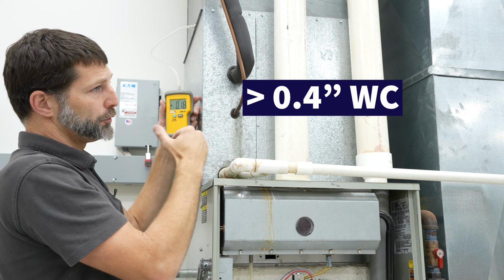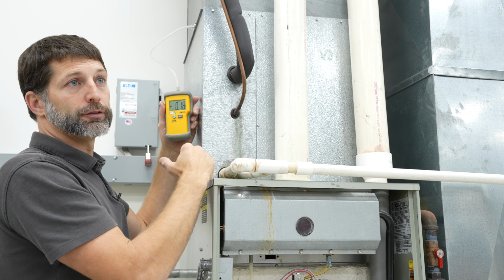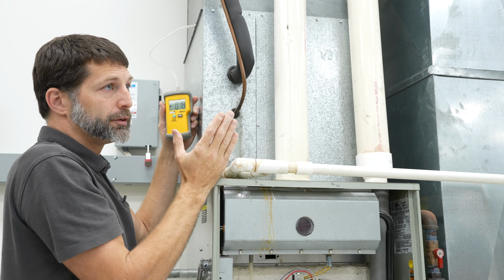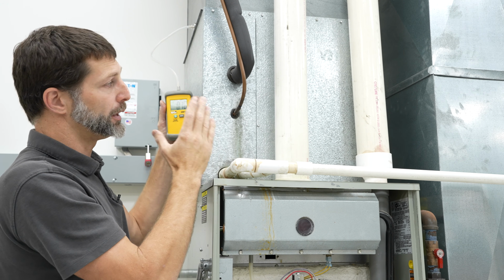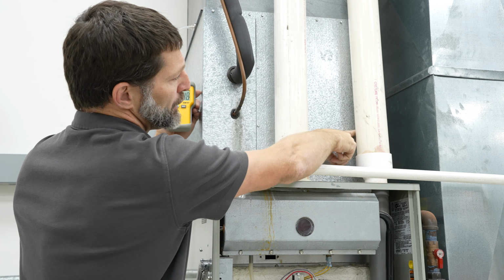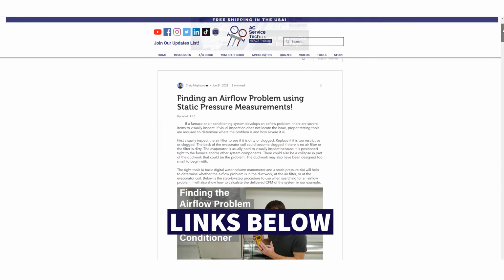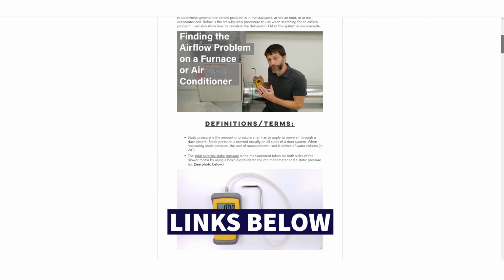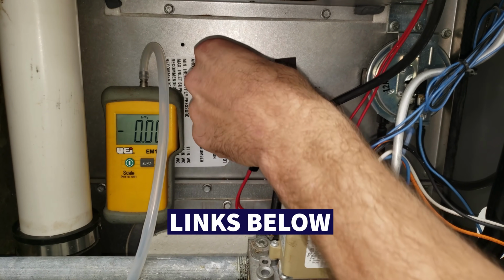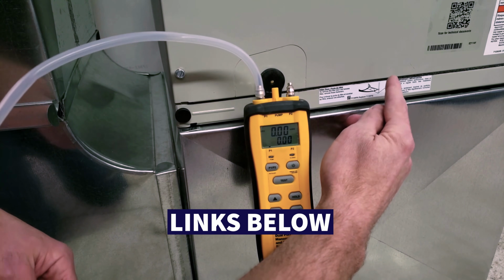Coils typically are never that high, and they could range anywhere from, say, 0.1 to maybe 0.4 or something around there, but you want to compare this to the manufacturer's literature to know. Now, if you want to learn more about measuring static pressure and total external static pressure, make sure to check out the video and article I have linked down in the description section below.